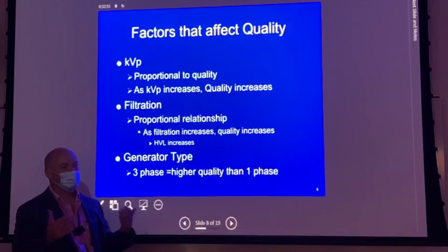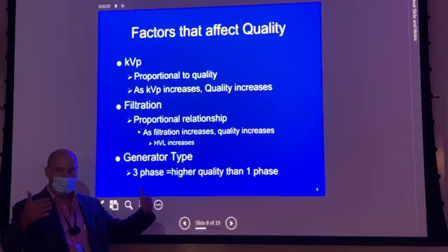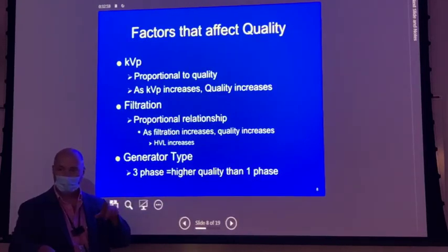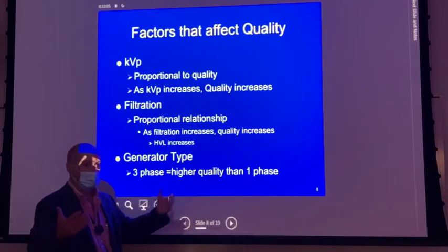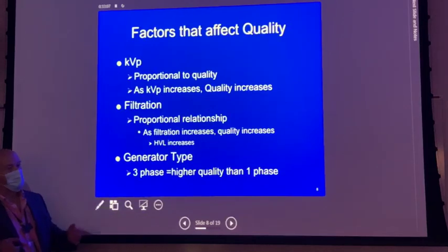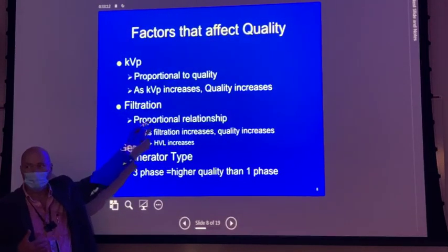And the line doesn't really seem to lose a whole lot of intensity in between exposures. So what that gives us is a higher average. Everywhere that you would come to a stop, you don't come to a stop, so the overall beam average energy increases. It works kind of like increasing kVp, not entirely, but kind of.